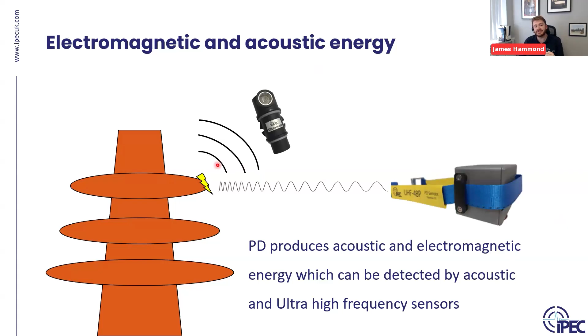You would have an acoustic microphone pointed at the terminations, often where you get surface partial discharge, and then a TeV sensor on the metallic cladding as well to detect those current pulses that way. Something like a dry type transformer, again, detecting surface tracking and TeV signals on the outer cladding is a method that we use.